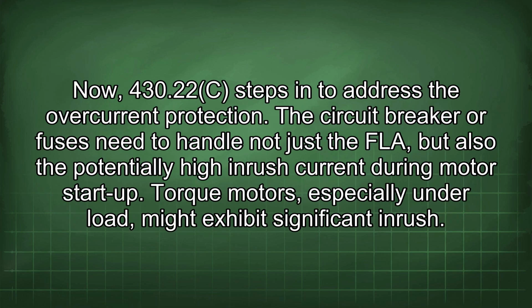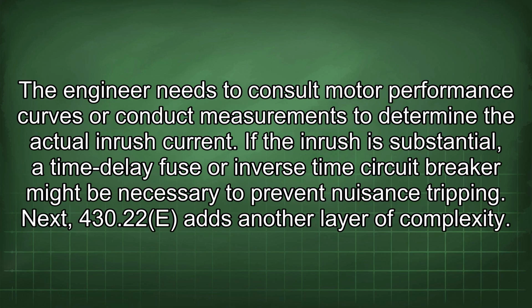Now 430.22c steps in to address the overcurrent protection. The circuit breaker or fuses need to handle not just the FLA, but also the potentially high inrush current during motor startup. Torque motors, especially under load, might exhibit significant inrush. The engineer needs to consult motor performance curves or conduct measurements to determine the actual inrush current. If the inrush is substantial, a time delay fuse or inverse time circuit breaker might be necessary to prevent nuisance tripping.